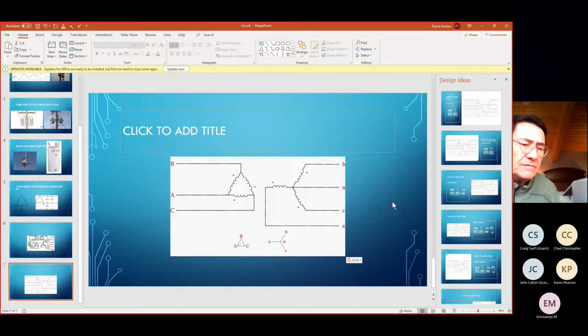Now, the second additional filter that is not necessarily power line is an EMC filter. An EMC filter is basically a tuned resistive capacitive circuit, kind of similar in its effect in that it is a voltage clipper, but it is tuned for much higher frequency absorption. The EMC filters, if you were buying the European brands, typically will come standard, because the European community has much stricter rules with regards to emitted high frequency noise, so these manufacturers just include them as part of their manufacturing process. In the United States, we don't have those same rules. Yaskawa manufactures in the United States, and so we manufacture to US rules, and the EMC filter is an option.